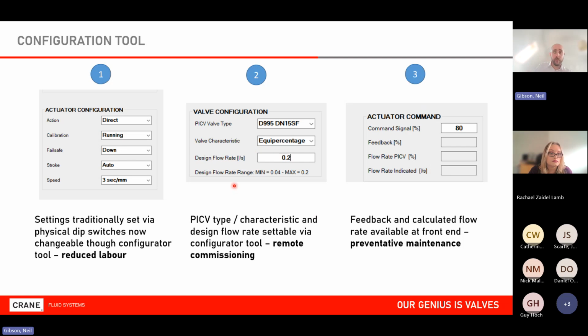So this is a configuration tool that you can download from our website. These are just effectively all of the Modbus registers in a nice, easy-to-use format. So we don't have to go looking for the register and what values I need to input. We do have all of that information in our IOM. This just simplifies the process. And you can see it's as simple as a drop-down box. So I can switch it from direct to reverse acting. I can select the valve type I'm on, that's all stored in here, and I can input the flow rate. It even tells me what the minimum and maximum for that valve is.